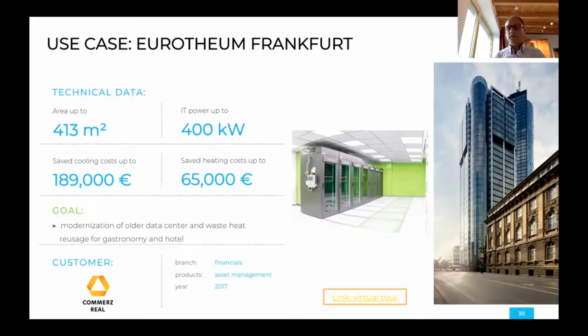So we took over the data center. We said we would put our data center inside that building if we were allowed access to the building's heat system, allowing heat recovery from our servers. The owner, Commerz Real, agreed, and we were very happy because now we could renovate the data center and put liquid cooling into it. Now we pipe the waste heat of the servers into the heating system of the building, and in winter we supply heat demand to the building. In summer, there are 8 floors of hotel up in the skyscraper, so we can provide warm water for the spas and showers for the hotel.